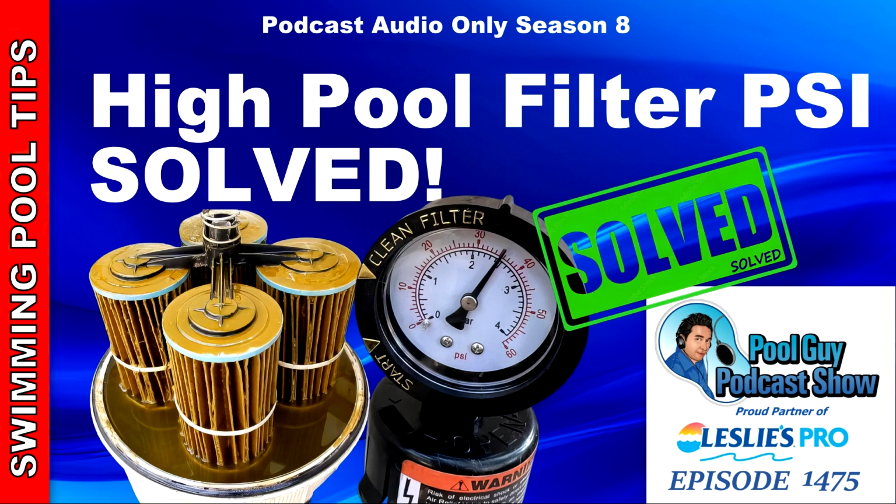although I've had really bad pools impact the cartridge filters. Usually the water quality and the filter PSI on a sand filter and a DE filter are a direct correlation. In other words, the worse the water quality is, cloudy, kind of greenish or milky blue, the higher the filter PSI will be on those filter types.